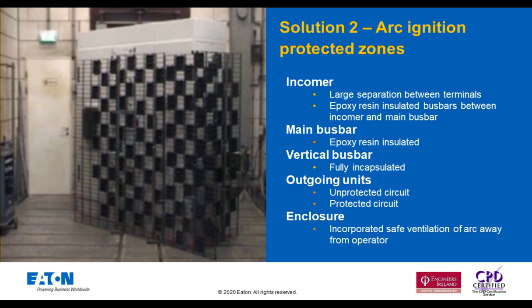As you may notice on the picture, at the top of the switchboard there's a pressure relief roof that opens during arcing conditions, and the ionised gases vent upwards and away from the operator. And obviously the IP of the switchboard is still maintained after the event. And as I mentioned, the cotton indicator pads are representing the personnel standing in front of or to the side of the switchboard during the arcing effect.